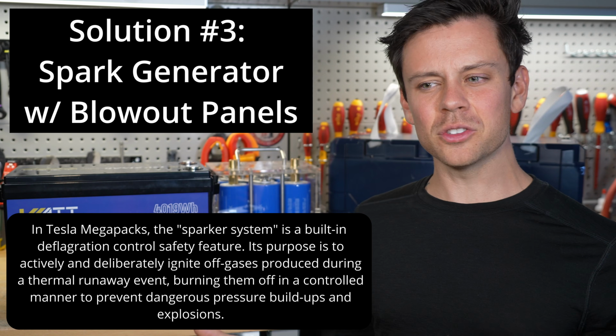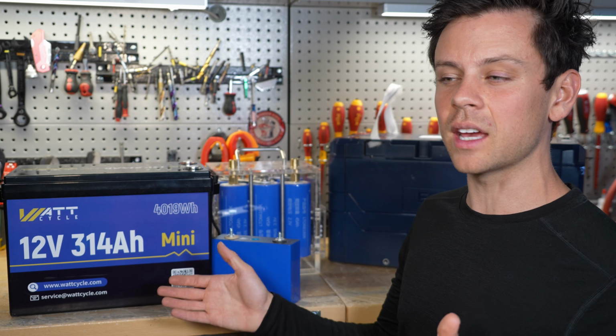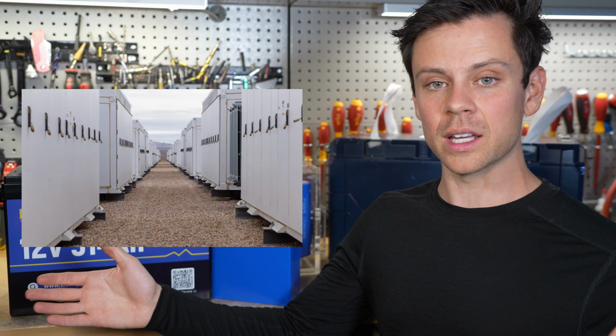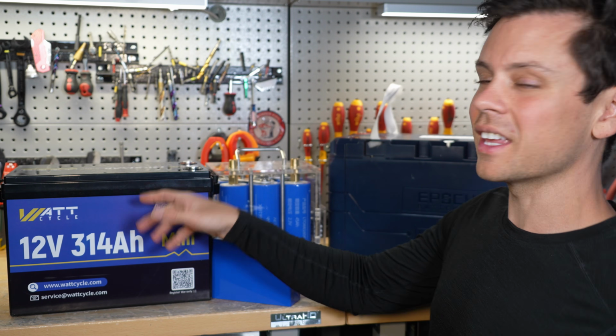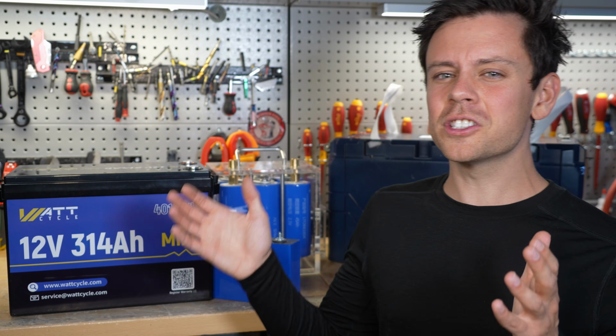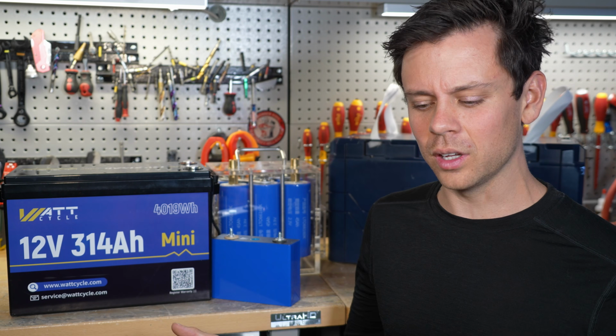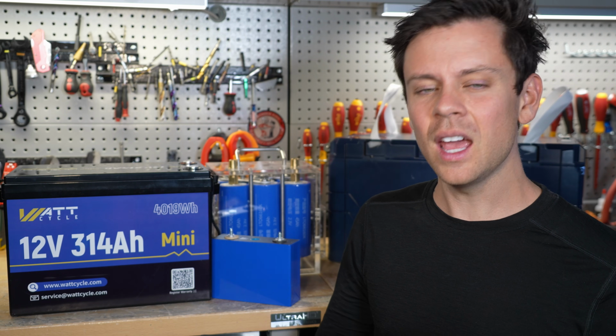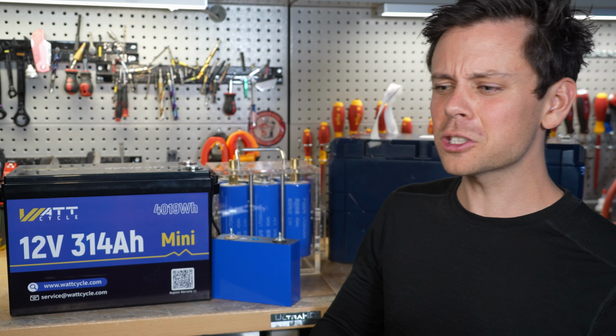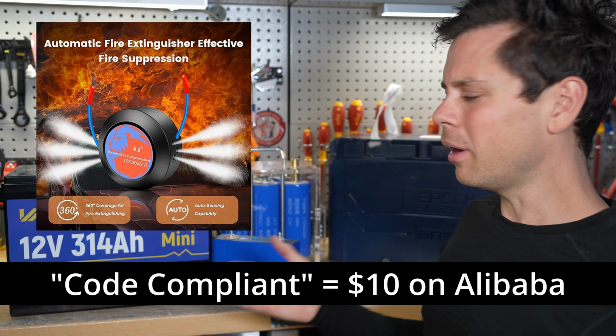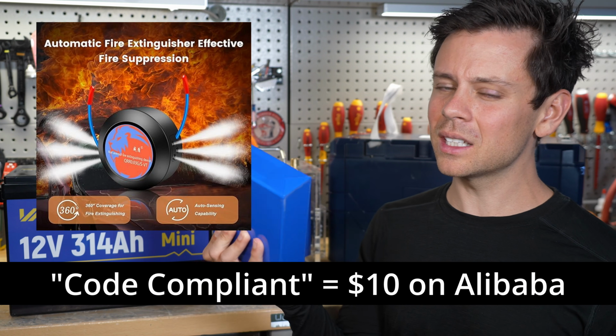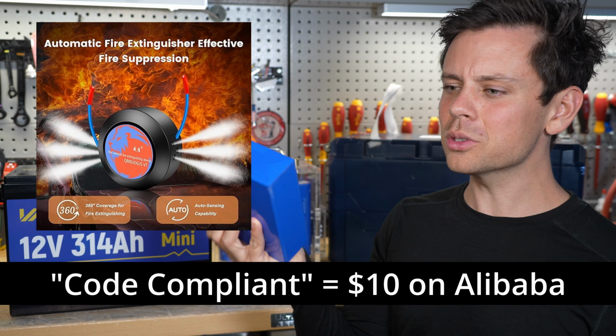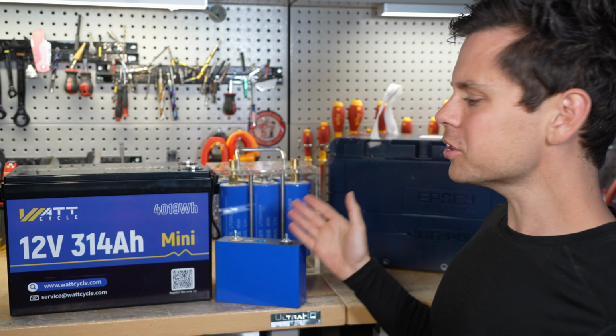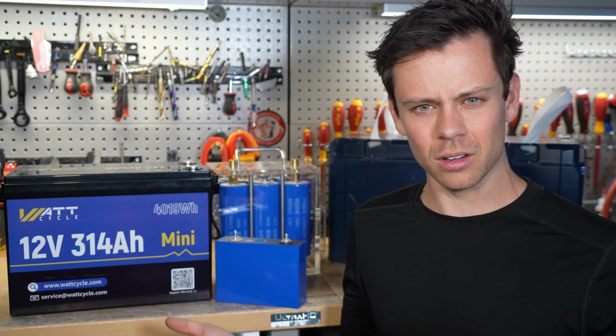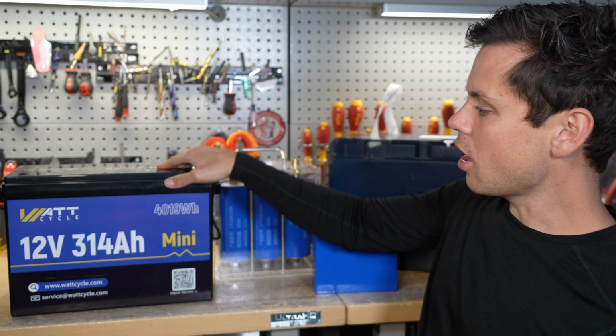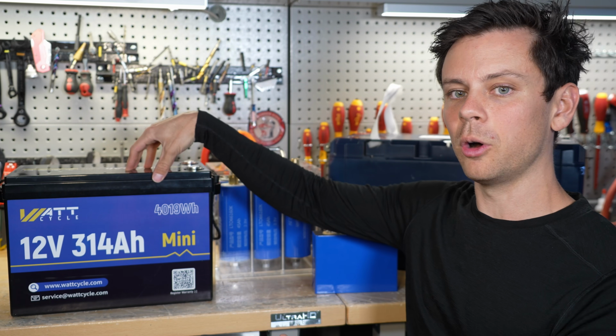Now something that confuses me is all the solutions I just mentioned are on large batteries for the grid, but small consumer batteries don't have that. Even large consumer batteries like a Tesla Powerwall, even if it's CEC listed and UL 9540, they'll just put some fire extinguishers in there. But LFP has very limited combustibility, so what use are those fire extinguishers? They don't seem to help with the explosion risk at all. It seems like the most dangerous ones are the sealed case ones, like these small budget batteries.